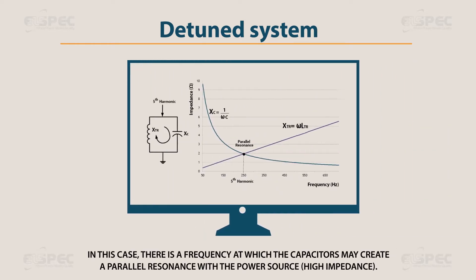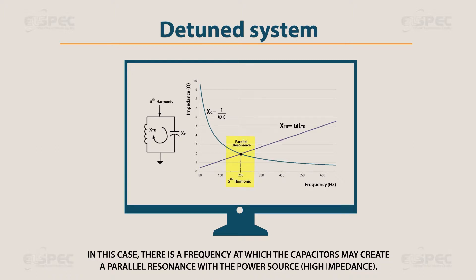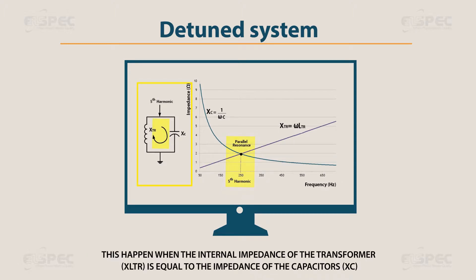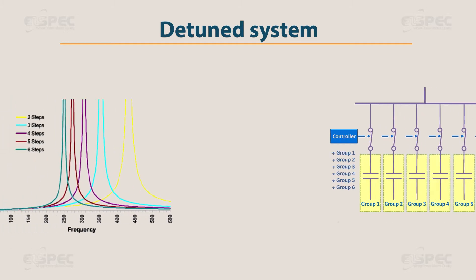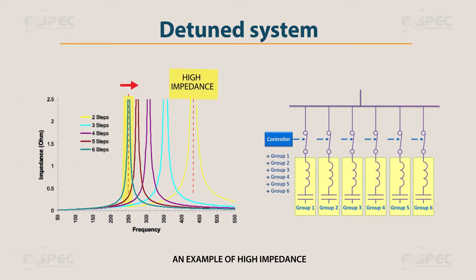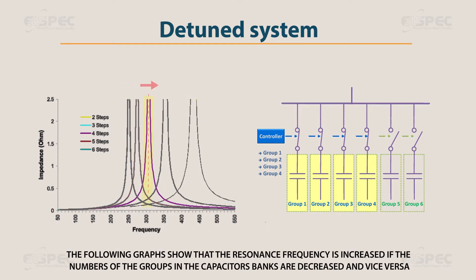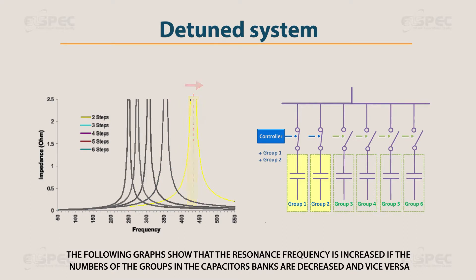In this case, there is a frequency at which the capacitors may create a parallel resonance with the power source — high impedance. This happens when the internal impedance of the transformer (XLTR) is equal to the impedance of the capacitors (XC). The parallel resonance creates very high impedance at the resonance frequency. The graph shows that the resonance frequency increases if the number of groups in the capacitor banks is decreased, and vice versa.